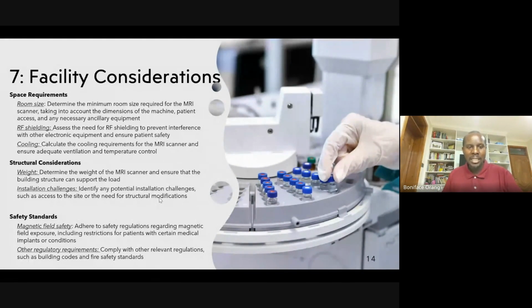The other bit that is very important, and maybe Kennedy might touch on it, is cooling. Cooling is the most critical for your MRI. Remember, Kennedy has mentioned that we are applying superconductivity, where we are reducing the resistance of copper almost to 0. By reducing the resistance of copper almost to 0, it allows us to generate the kind of magnetism that we do. That's why we call it superconductive. You're taking your normal conductor, which has resistance, and taking away the resistance to ensure it's superconductive. And to do that, you need to cool.